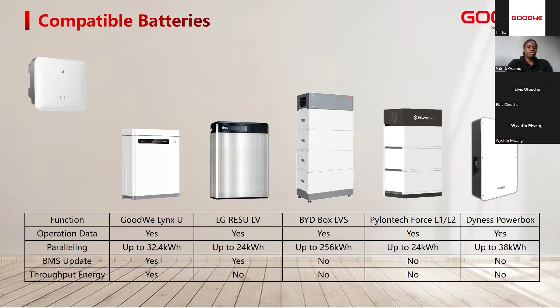Next in line is to focus on the low voltage battery system that the ESG2 uses. In this sense, we'll focus on the GoodWe lithium phosphate battery, called the Lynx U series, which comes with a number of key features. To begin with, a single unit of Lynx U battery is 5.4 kilowatt hour. You can scale up these batteries to give you a maximum of 32.4 kilowatt hour installed on a single ESG2 inverter. The Lynx U is a low voltage battery, with voltage operation at around 40 volts. During the scaling up, Lynx U has module auto recognition integrated within, so no dial setting is required for the scaling up or expansion of your battery system. The battery itself has the capability of remote diagnosis and update of its firmware and communication protocols.